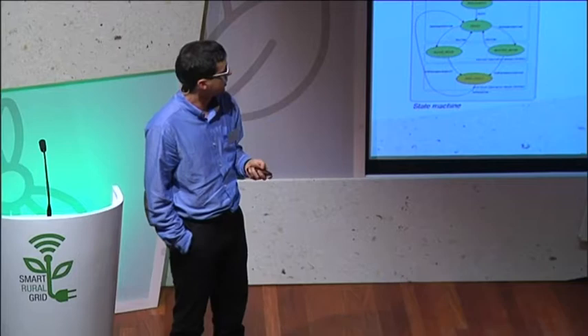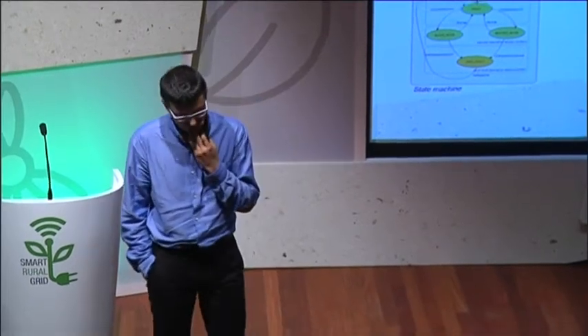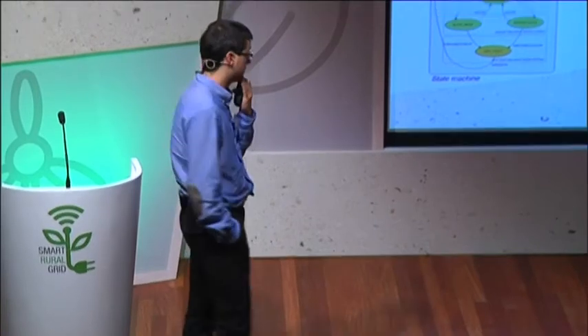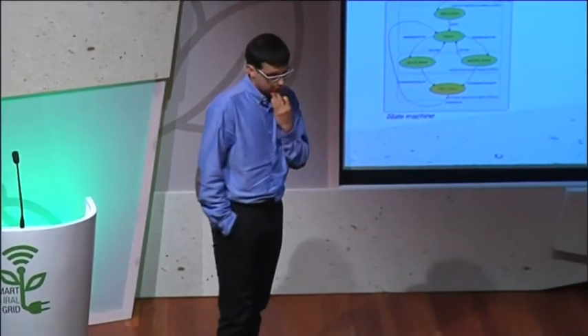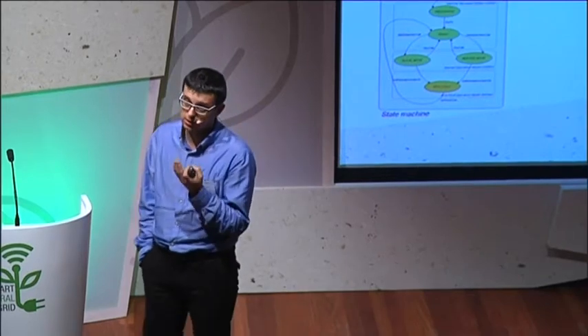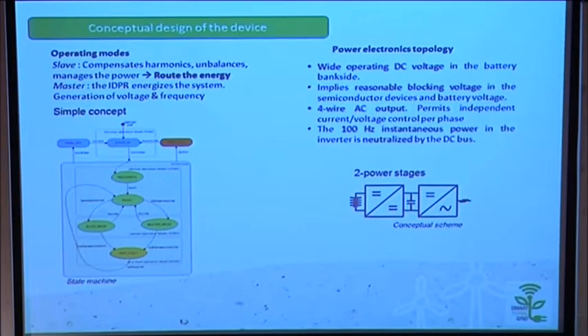About the power electronics, we decided to adopt a 2-stage power electronics scheme, because the IDPR can operate with a battery storage system connected, or without one. In case we connect a battery, we want to be as flexible as possible, meaning we want to connect different technologies and different voltage levels. The first stage is used to boost the voltage, so we have the required voltage to operate the AC side, which is the important part at the end.